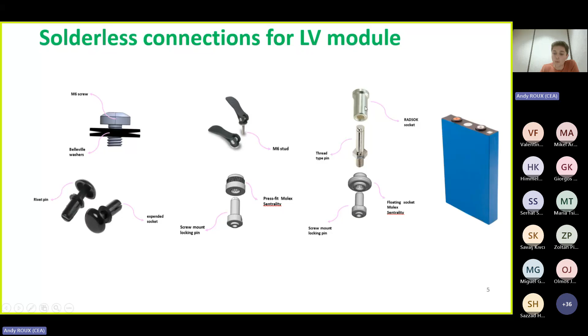For each connection, we used our test bench. We have 2 power cables connected to manufactured fake tabs, and on these fake tabs we put our solution, with the contact made by our bus bar with the solution integrated in it. We have temperature measurement and voltage drop measurement placed on the connection to see the voltage drop around it.